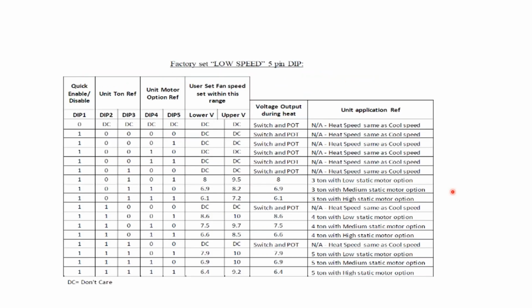All right, so if you have a single phase unit, you're going to have, as we talked, the additional 5 switches. We've got the quick enable dip switch 1. So if dip switch 1 is off, dip switches 2, 3, 4, 5 don't do anything, and the heating speed remains the same as cooling. Now, let's say we've got a 3-ton unit out of the box with a low static motor option. That unit should come set with dip switch 1 on, 3 on, which tells it what tonnage unit it is, and 5 on, which tells us the low static motor combination. So that's what 2, 3, 4, and 5 do.